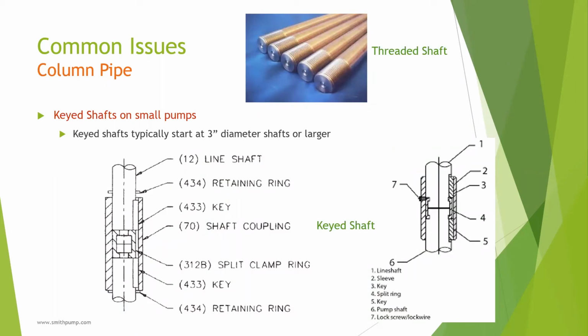Keyed shafts are a great way to transmit torque between two rotating pieces, which is why we normally see keyed shafts on motors. So if this is common practice, why don't vertical turbine manufacturers key all line shaft connections as standard? As you might have guessed, it's mainly because of price. Threaded shafts are simple and less expensive to manufacture. They transmit the torque and resist downward thrust from a spinning impeller. However, somewhere around the 3-inch shaft diameter, threaded shaft connections are much harder to break apart and they have a tendency to gall together. So this is when the more expensive keyed line shaft is typically needed.